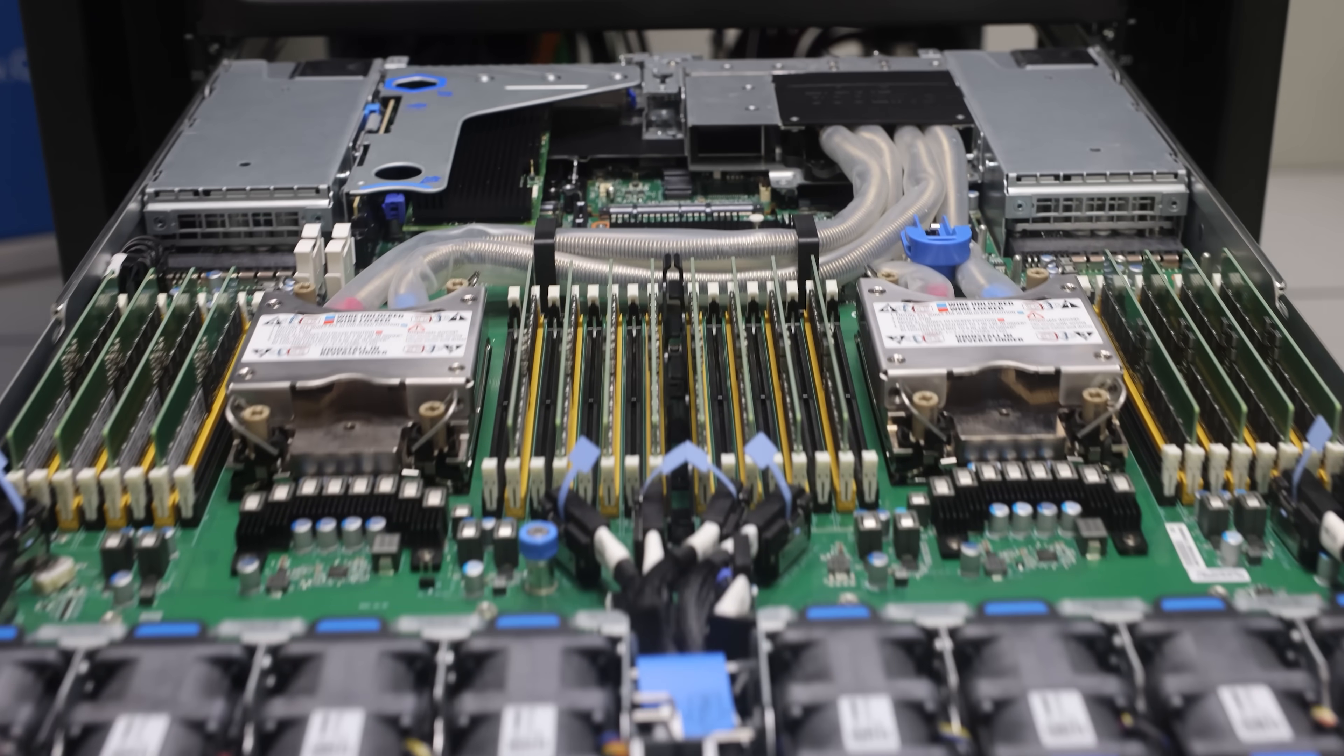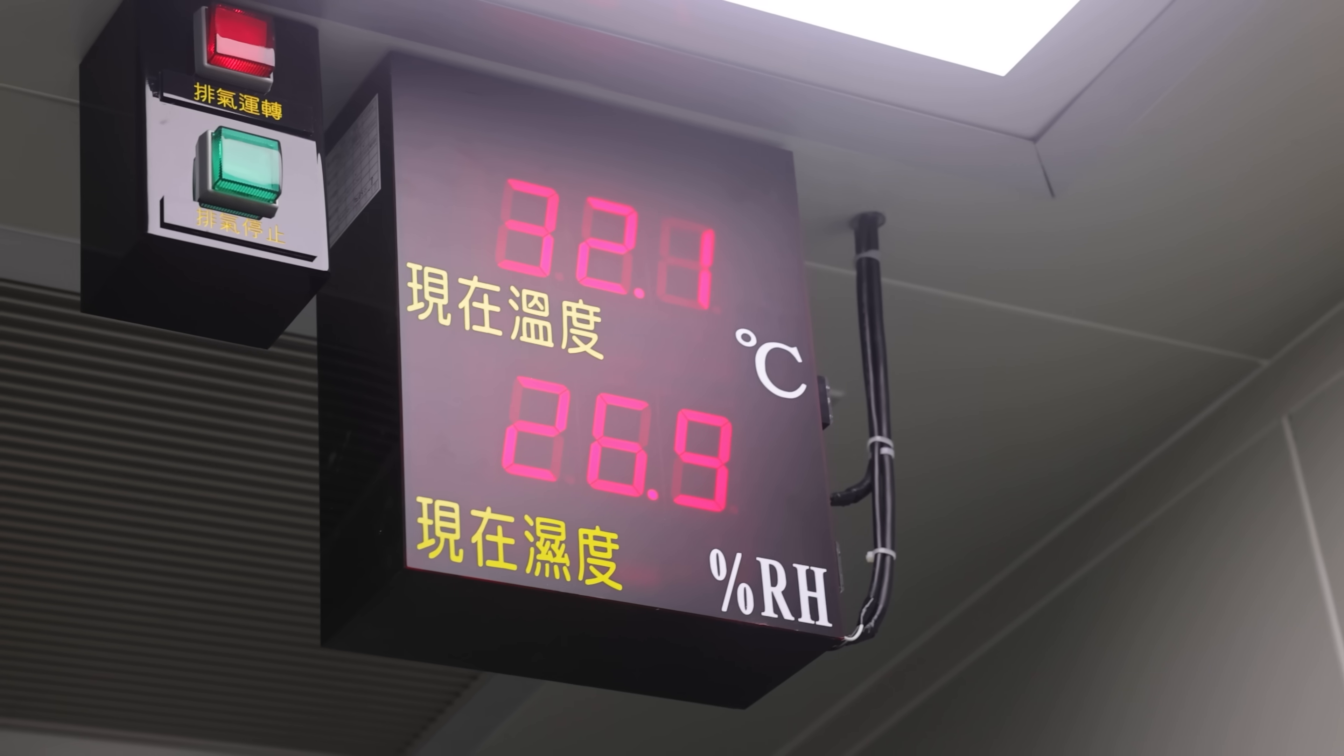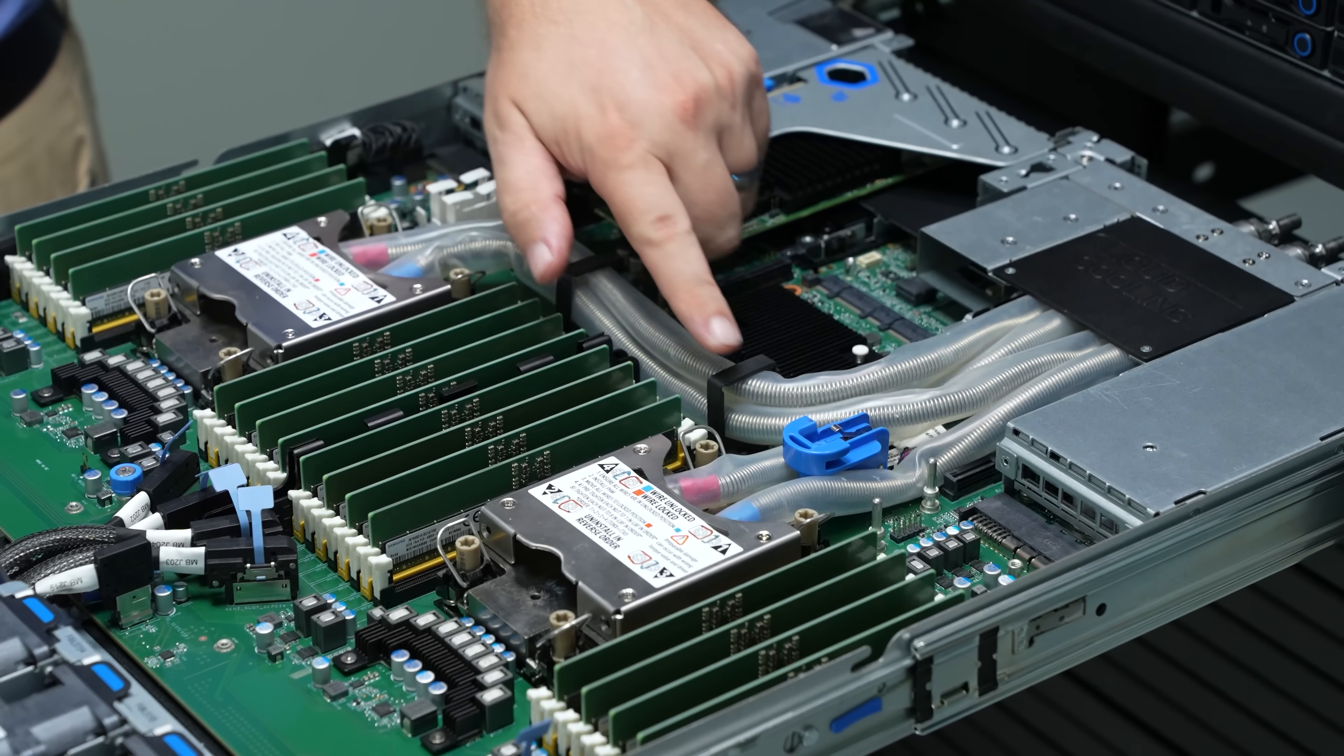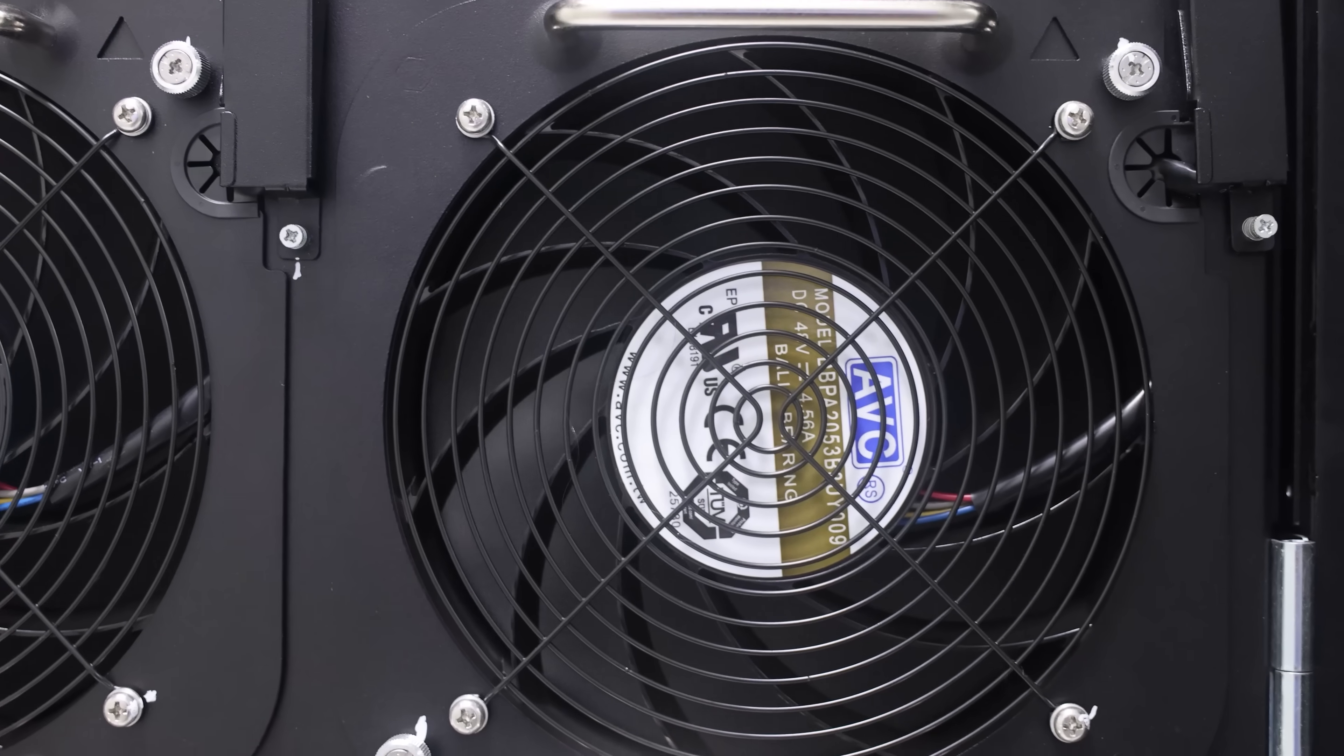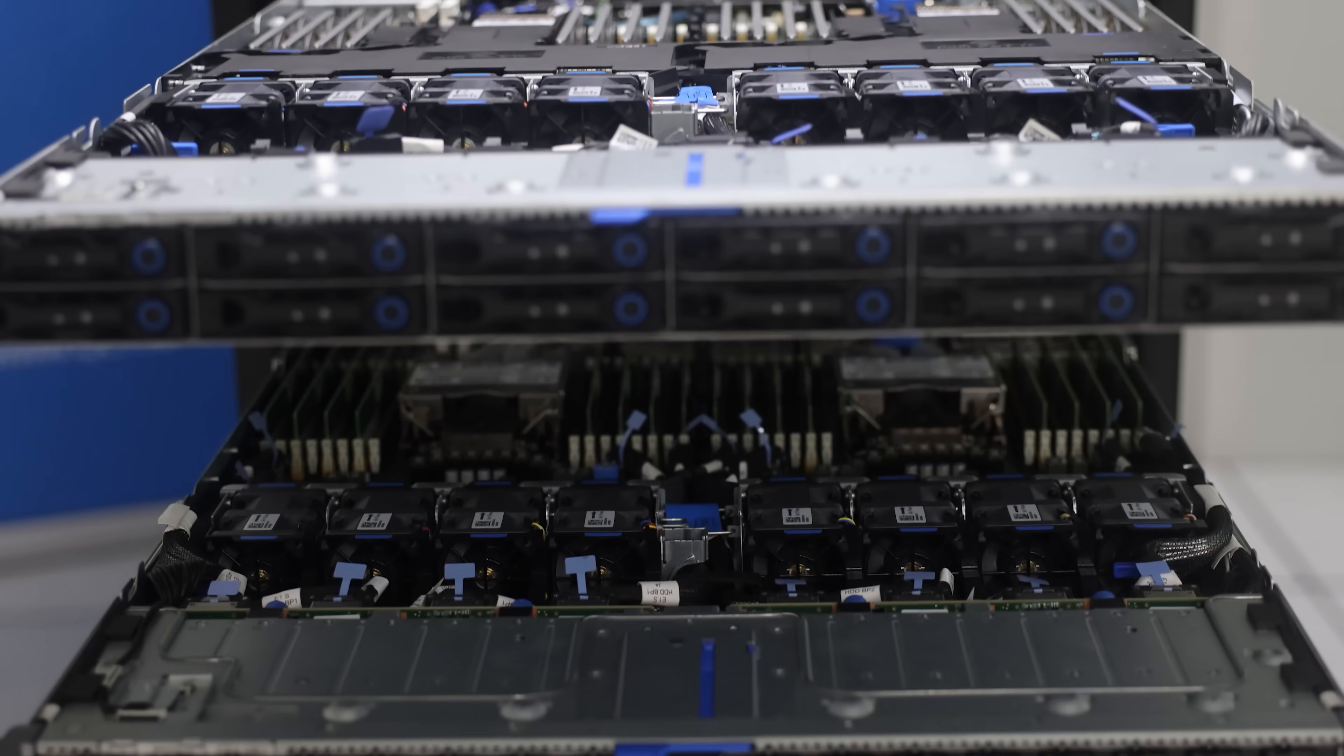Liquid cooling is a huge topic in the industry right now. Modern processors use so much power that we're not talking about like a 1% or 2% power consumption savings by using liquid cooling versus air cooling. Instead, you can be talking about 10% or more of power consumption savings per server just based on using liquid cooling versus traditional air cooling with fans and heat sinks. Or another way to look at it is for every 10 servers, you get to have another one running for free, or well, kind of.